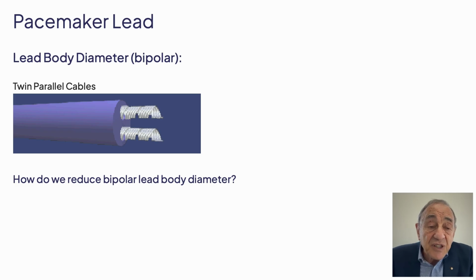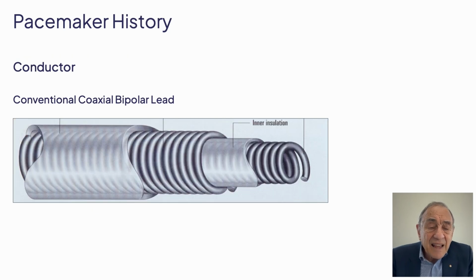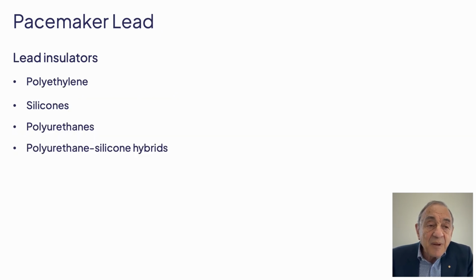How do we then reduce the bipolar lead body diameter? We use changes to the conductor or to the insulator. The conductor change that occurred was the conventional coaxial bipolar lead you're all so familiar with today. There's a central cathode, insulated, and then the outer anode, also separately insulated. The materials used, as we said earlier, was polyethylene. Then we introduced silicones and then polyurethanes, and today we also use hybrid materials.